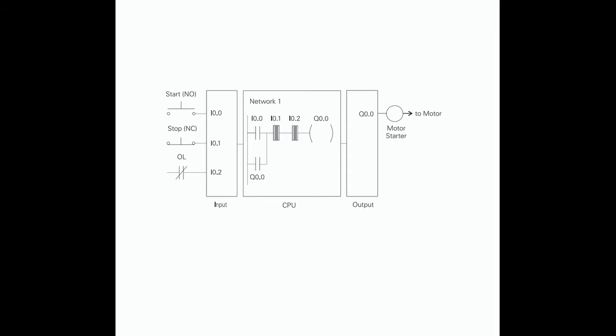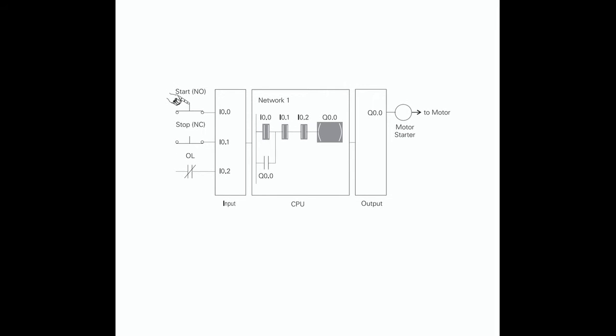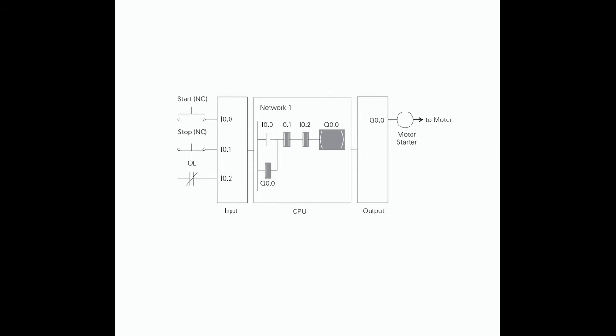In addition, a normally open set of contacts associated with Q0.0 is programmed on network 1 to form an OR circuit. A motor starter is connected to output Q0.0. When the start push button is depressed, the CPU receives a logic 1 from input I0.0, causing the I0.0 contact to close. All three inputs are now a logic 1, and the CPU sends a logic 1 to output Q0.0. The motor starter is energized and the motor starts. On the next scan, the normally open contact Q0.0 closes and output Q0.0 will stay on even if the start push button has been released.